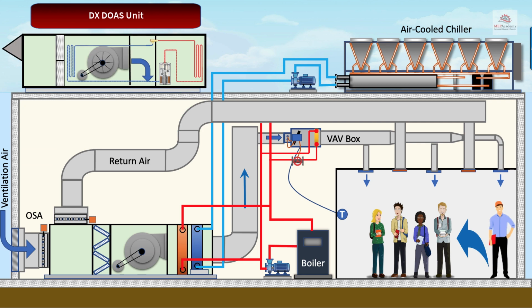If we install a DX dedicated outside air unit on the roof to handle the ventilation air and remove the outside air louver and duct from the indoor air handler, then all the latent load for the ventilation air will be handled by the DOAS unit.